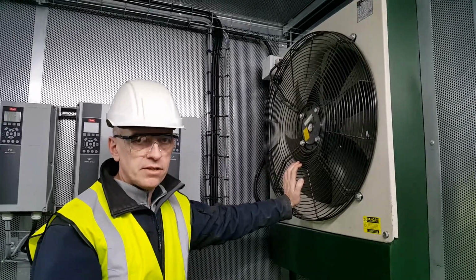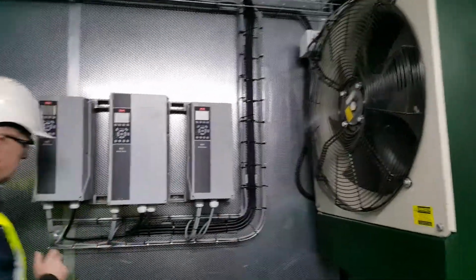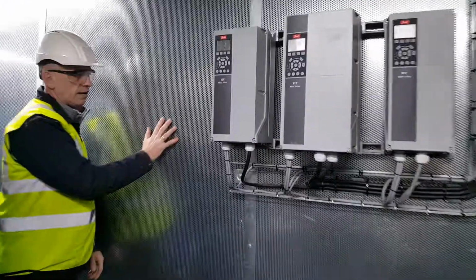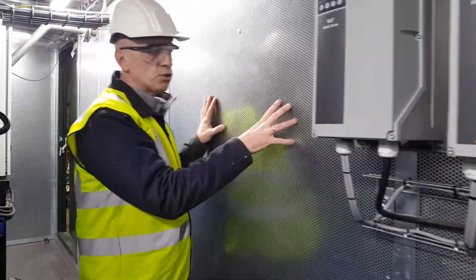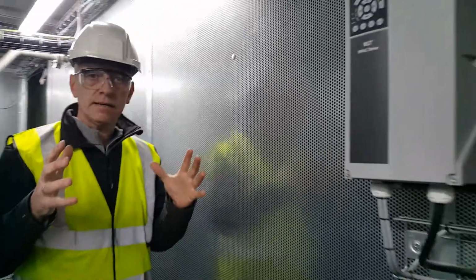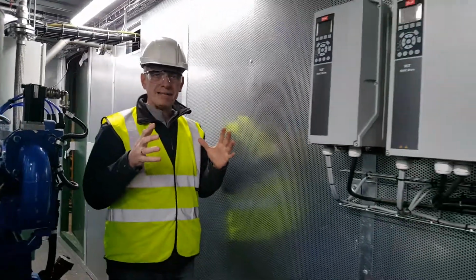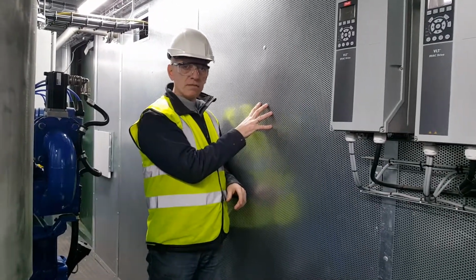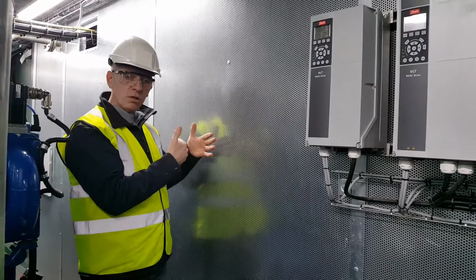Again, it's a standard ISO container. What we've also done, unlike other container manufacturers, is use 2mm perforated steel. To attenuate noise you need mass, so first of all you're hitting 2mm steel rather than 1mm or 0.85mm. Then we have 100mm of rock wool, and then the external skin of the container.